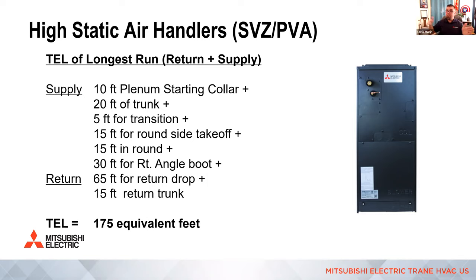And in this example, we had 20 feet of trunk duct. And in that trunk duct, we actually can't run just the same size trunk. We have to reduce the trunk size in order to keep the velocity up, right? So typically every 2 to 3 takeoffs, and that's another rule of duct design, we end up downsizing the trunk in order to get the velocity back up above 700 feet per minute, right? Every time we downsize the trunk, on the back of your duct calculator in the extended plenum fitting section, you'll see a trunk reducer. It's 5 feet for each transition down. There's a little bit of restriction there to get the velocity back up. If we had 2 transitions in that trunk, then we would account for 10 feet, right?